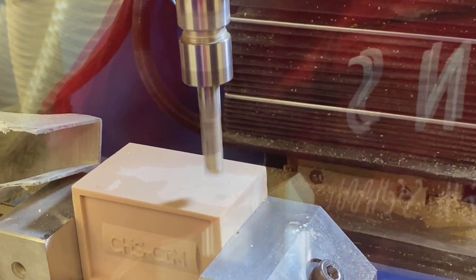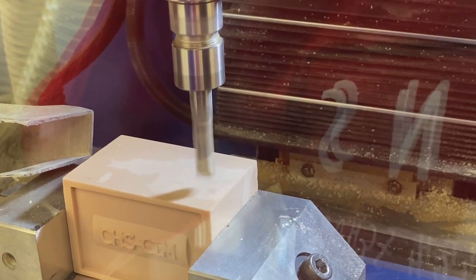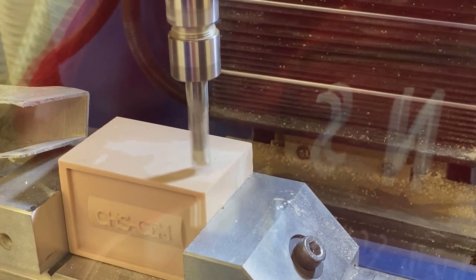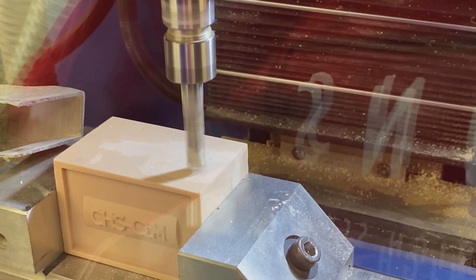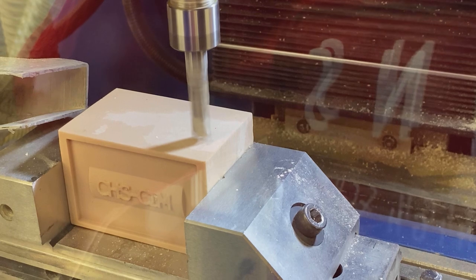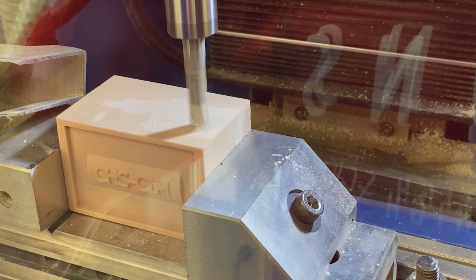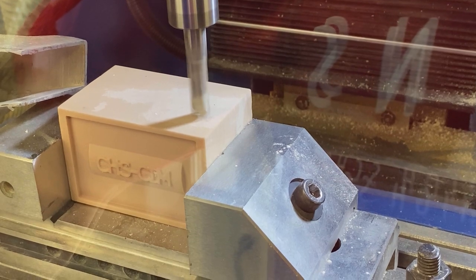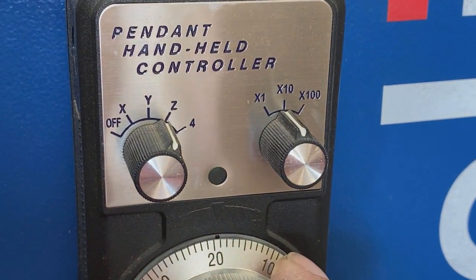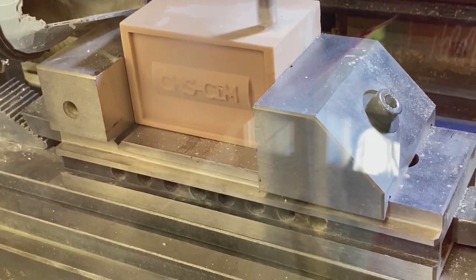There's a couple different ways to do this. This is the simplest. So I'm just going to keep coming down, so it just touches the top of the block. I can't use the probe here like I did on the tool setting because the probe needs a conductive surface and this block is not conductive. So I've got this set to my times 10 value, and I'm just tiptoeing down.